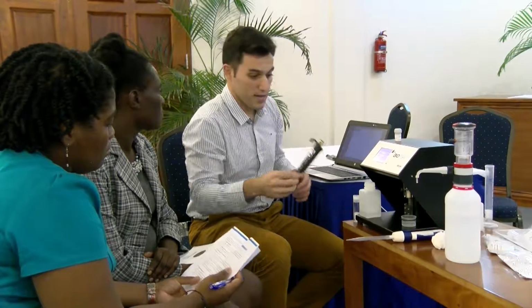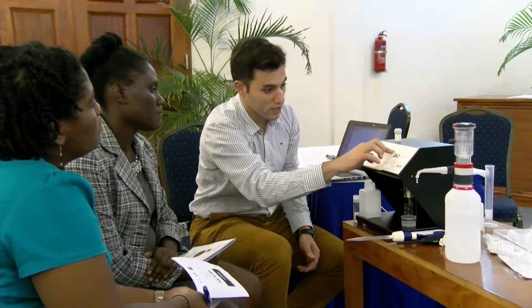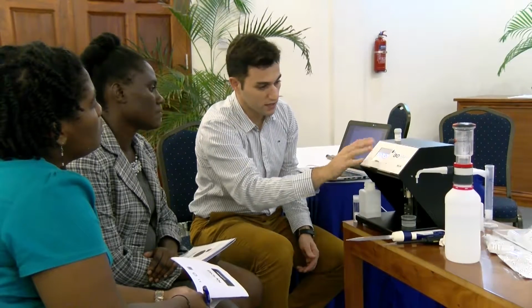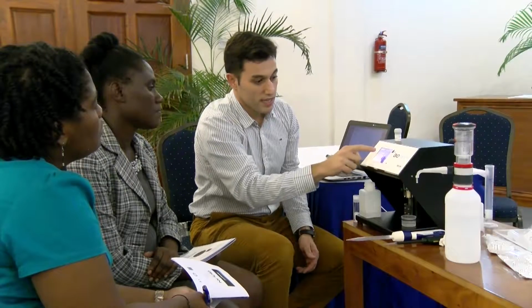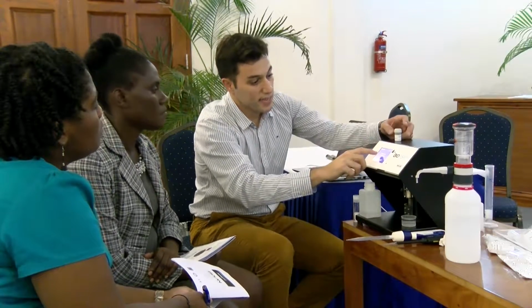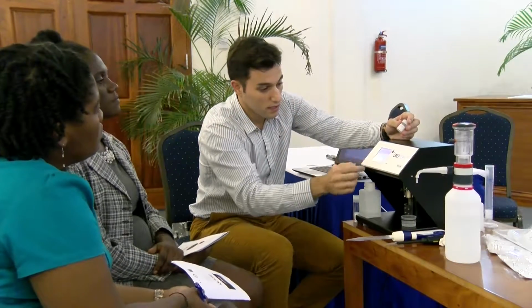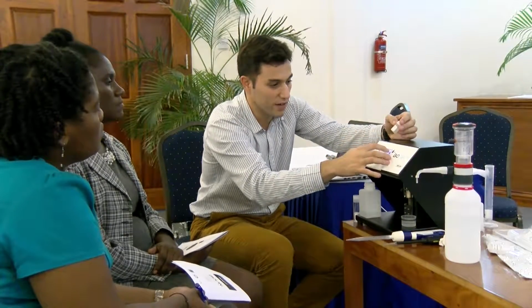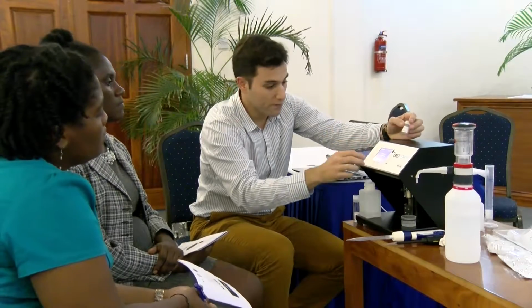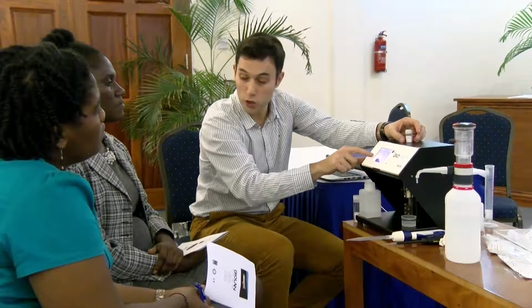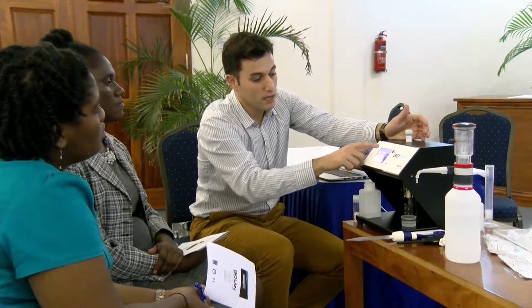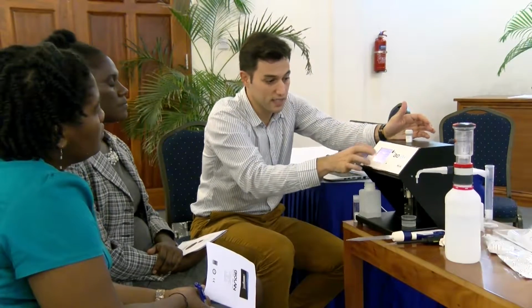Okay, we can use it. Basically, normally we should switch it on. We mount the reference electrode and the working electrode. We can switch it on: 2 seconds pressing the button, it starts. Okay, biotest. Histamine, sulfite, histamine. Choose. This is the code of the biotest that is printed here. If we want to change to a new biotest, we have to write down the code. The device will know the number of analyses on the biotest. In this case, we've made 3 analyses and we have 47 analyses more. Okay, we go ahead. Fish meal, salted fish. In this case, fish. Now the biotest is already set up. Now let's go to analysis.